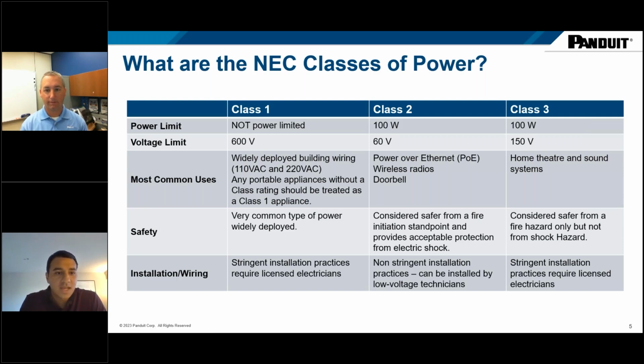600 volts and widely deployed. It's really the kind of electricity that's running in our buildings today, 110 or 220 circuits, and it is stringent in terms of installation requirements. So you do have to have an electrician install Class 1 circuits.